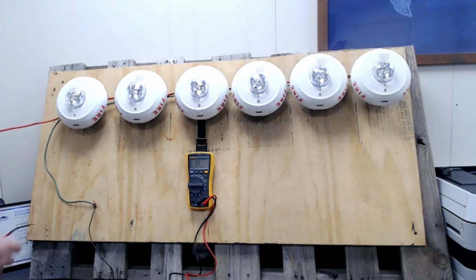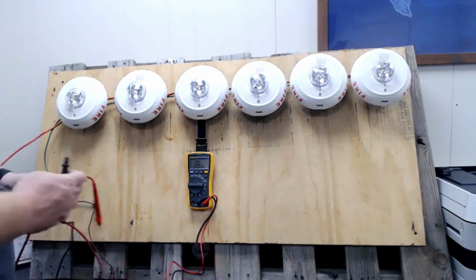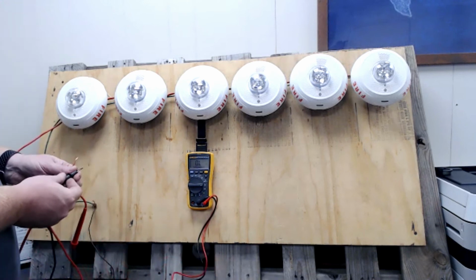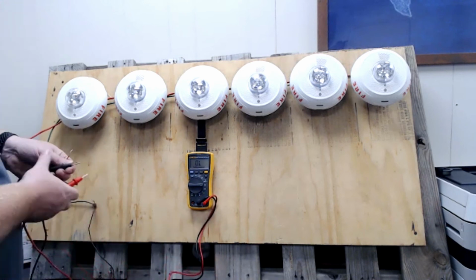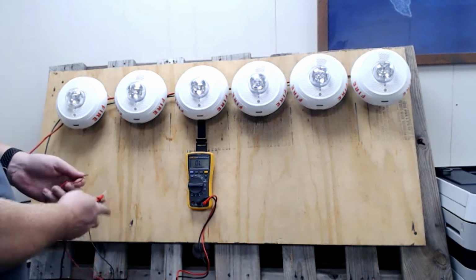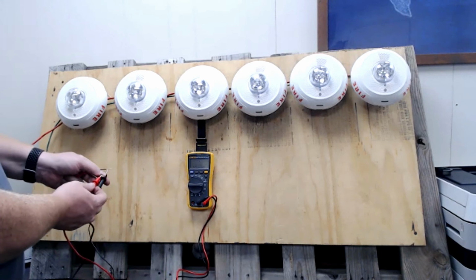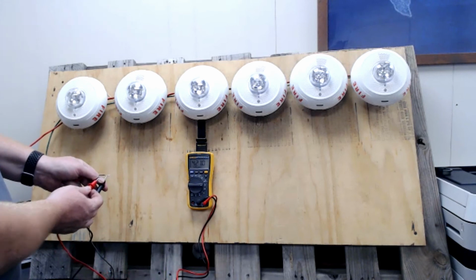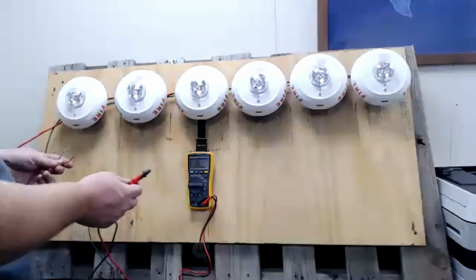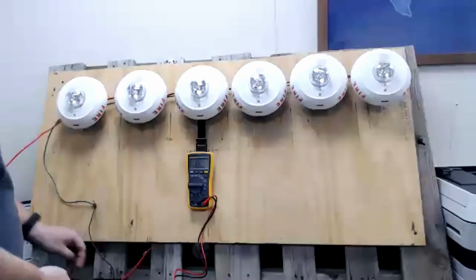Now, once more, we're going to verify all of our repairs, because now our circuit should be completely open and clear. And by that, I mean we should see the end-of-line resistor, no ground faults. All right, so I've got black meter lead to black conductor, red meter lead to red conductor. I see my 4.2 k ohms.